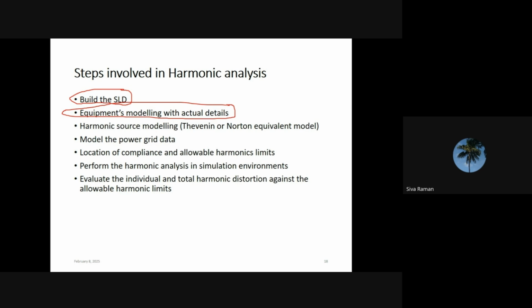What is the cable length? What is the size of the cable? What is the impedance of the cable? How many runs are we using for the transformer? What is the rating of the transformer? What is the impedance of the transformer? Whether any OLTC or off-circuit tap changer is there or not? What is the tap size? What is the tap step, etc.? We have to model all of this in the single line diagram.